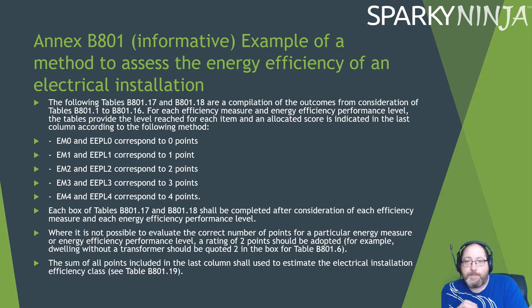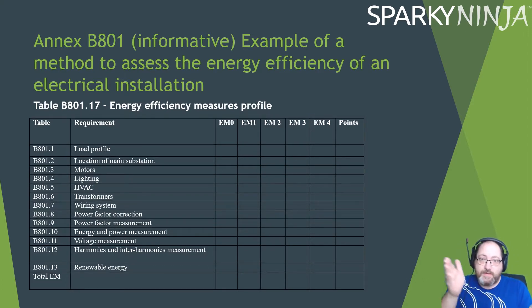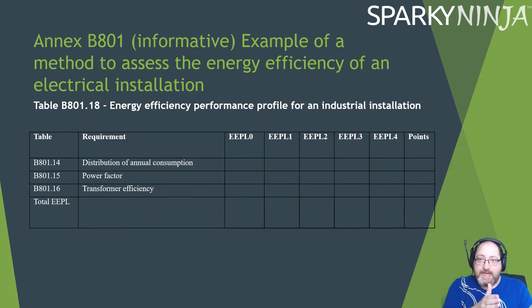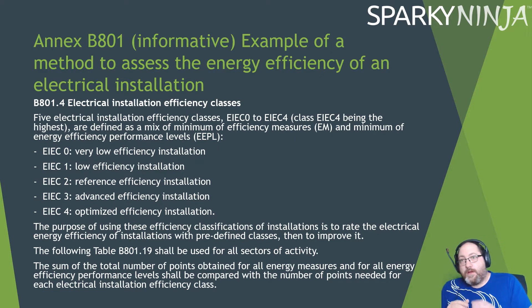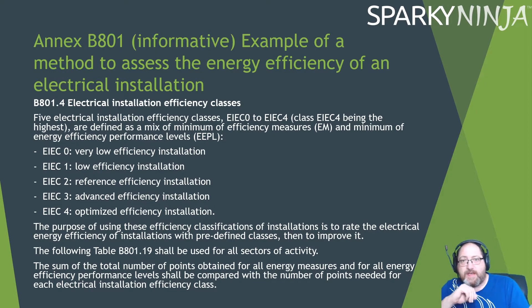The sum of all points including the last column is used to estimate the electrical installation efficiency class, done in table 19. The summary table lists load profiles, location of substations, motors, lighting, and other items down the left, with efficiency measure points and performance level points tallied up. There are five electrical installation efficiency classes, zero to four, defined as a mix of minimum efficiency measures and minimum energy efficiency performance levels.